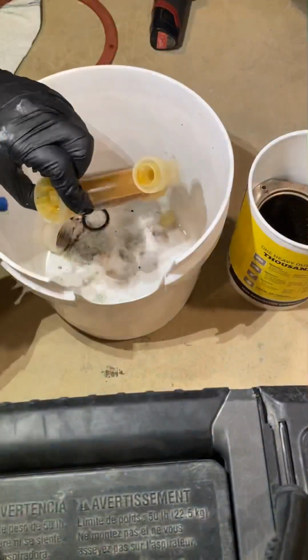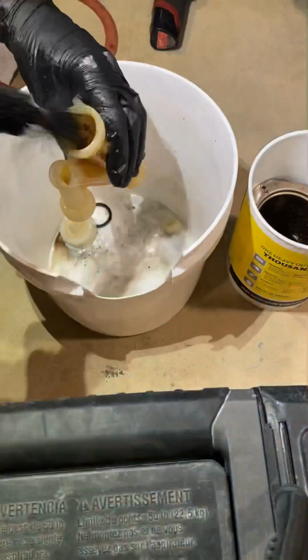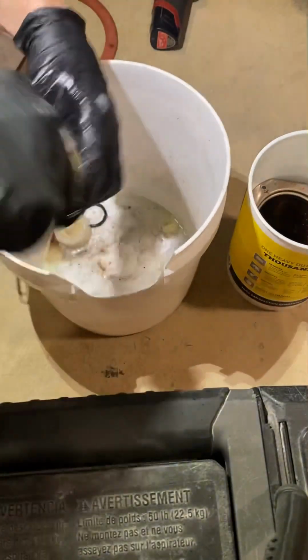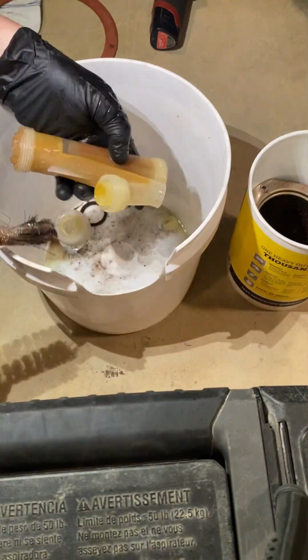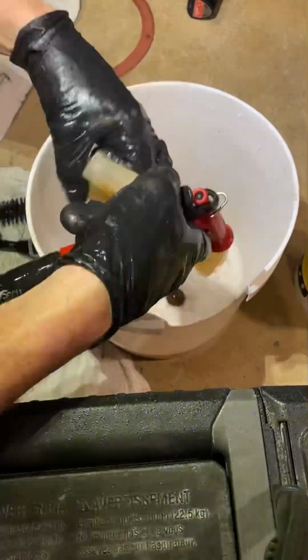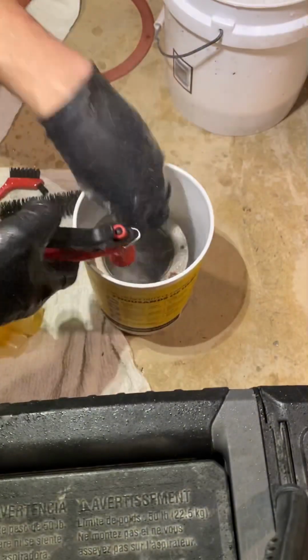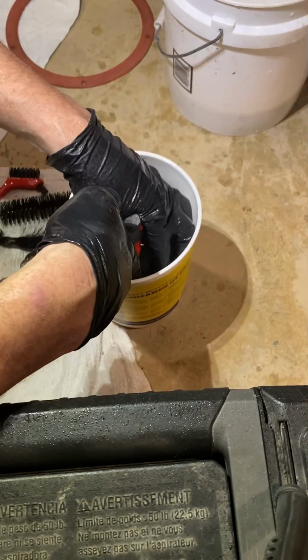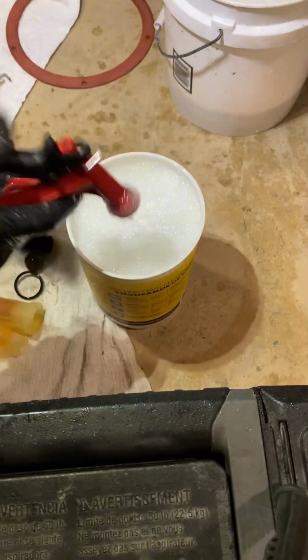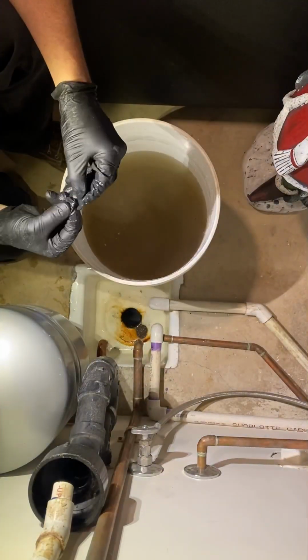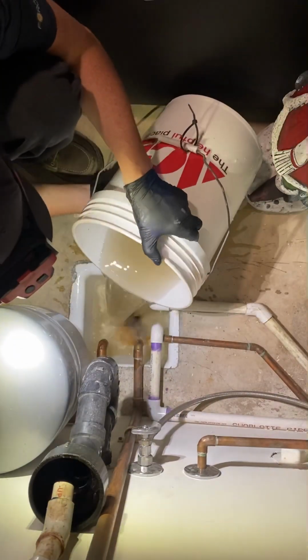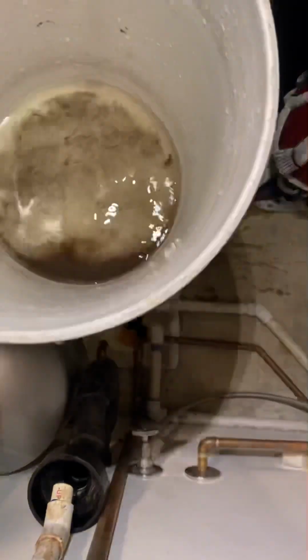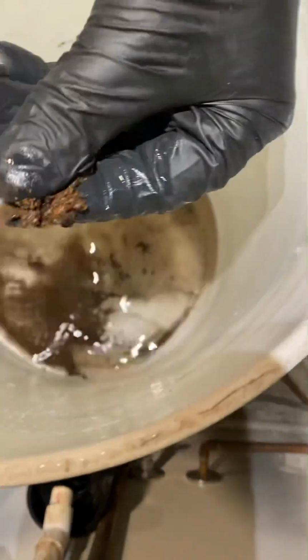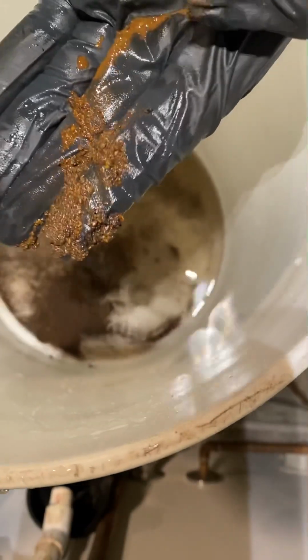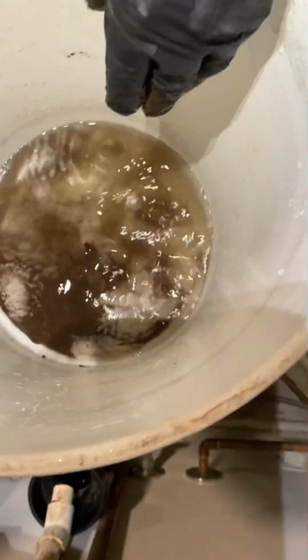Of course you know to clean all the parts before reassembly, but I'll tell you anyway just in case. Soak the condensate trap assembly and neutralizer, if there is one, with CLR. Blow the dust off the burner and soak it in a concentrated solution of Simple Green and water. It's always a good idea to check the bucket after cleaning the heat exchanger to see what kind of gunk you got in there. Kind of gives you an idea of how dirty the thing's burning and how often it needs to be serviced. We do it once a year anyway.